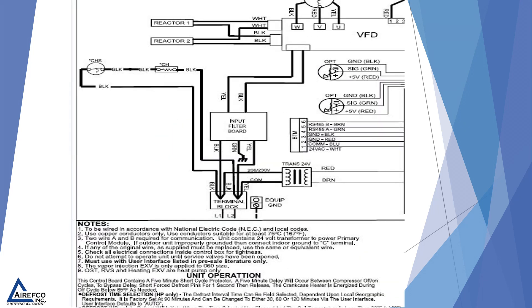Here we see a wiring diagram for a current inverter controlled heat pump. You'll notice that the crankcase heat is attached to the power side of the terminal block and is controlled by a crankcase heater switch, which is controlled by temperature. The notes of unit operation state the crankcase heater is energized during off cycle below 65 degrees as needed.